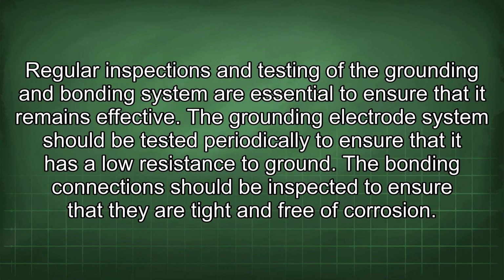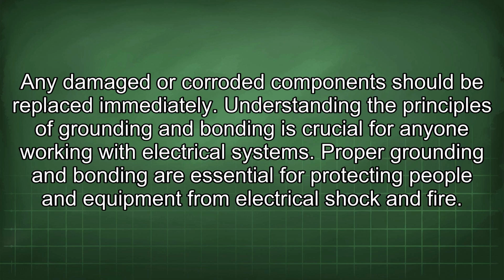Regular inspections and testing of the grounding and bonding system are essential to ensure that it remains effective. The grounding electrode system should be tested periodically to ensure that it has a low resistance to ground. The bonding connections should be inspected to ensure that they are tight and free of corrosion. Any damaged or corroded component should be replaced immediately.